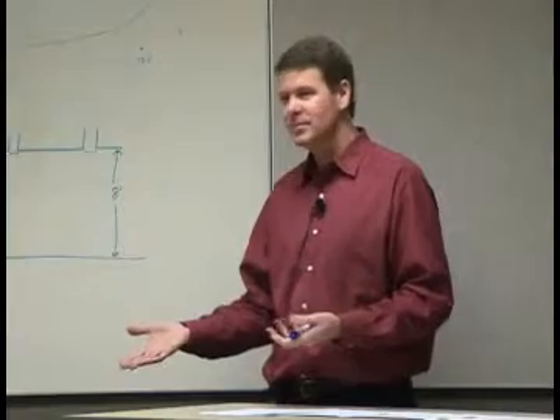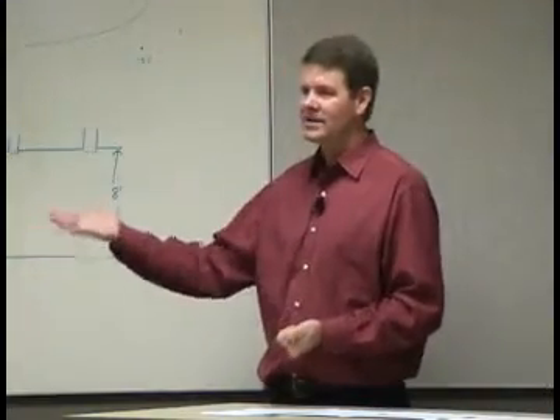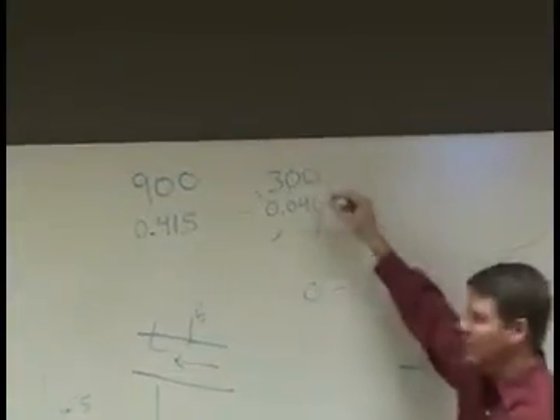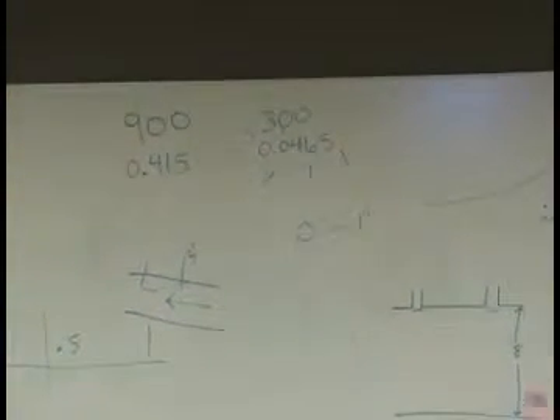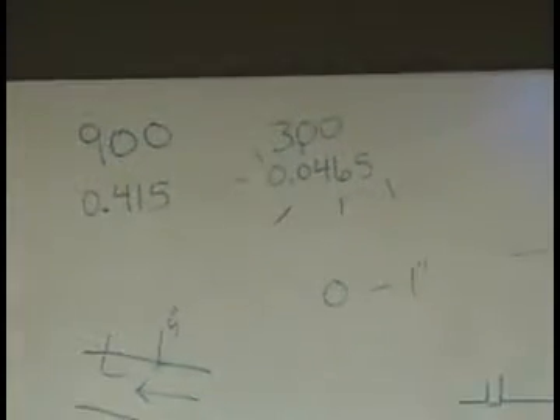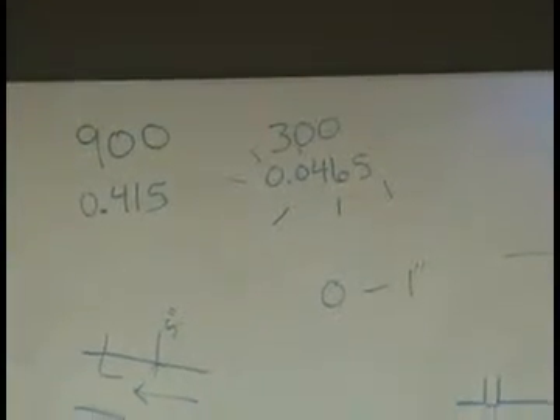Okay, it gets cold in the room. VAV box backs off to minimum. So we're here controlling at minimum, as low as we can. It's still cold in the room, so the reheat coil opens up. And now we've got 55-degree air coming from the air handler, goes through the reheat coil. It's got 150-degree water in it. We warm that air up to 120 degrees. We got nice toasty warm air coming out the diffusers.